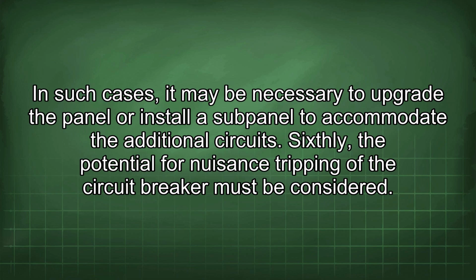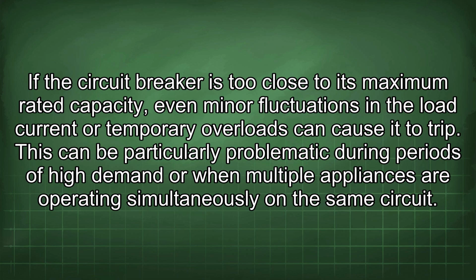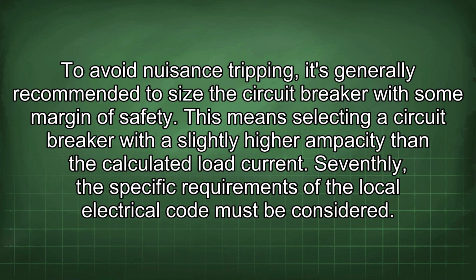additional circuits. Sixthly, the potential for nuisance tripping of the circuit breaker must be considered. If the circuit breaker is too close to its maximum rated capacity, even minor fluctuations in the load current or temporary overloads can cause it to trip. This can be particularly problematic during periods of high demand or when multiple appliances are operating simultaneously on the same circuit. To avoid nuisance tripping, it's generally recommended to size the circuit breaker with some margin of safety. This means selecting a circuit breaker with a slightly higher ampacity than the calculated load current.